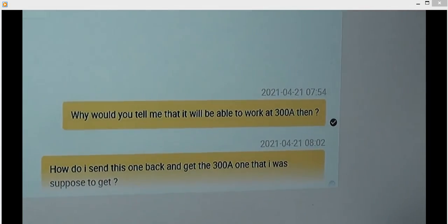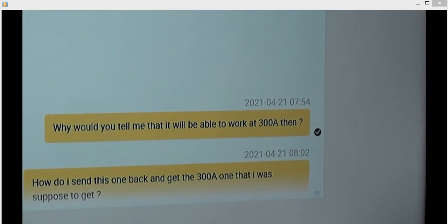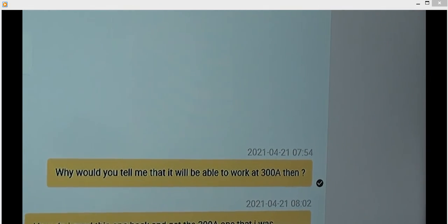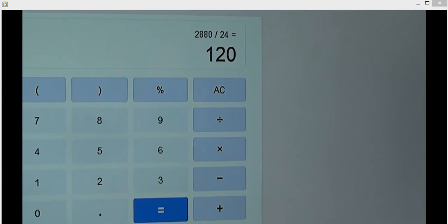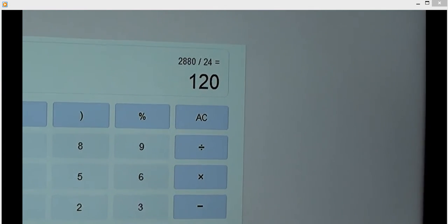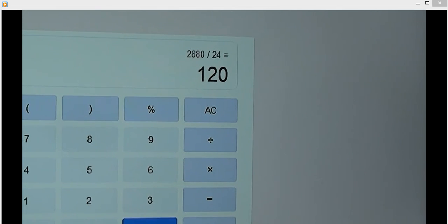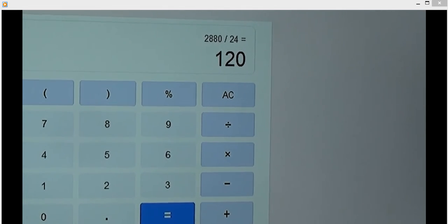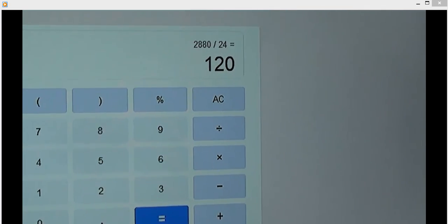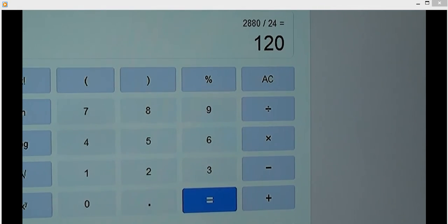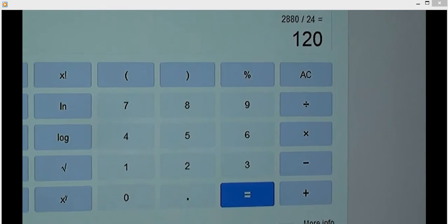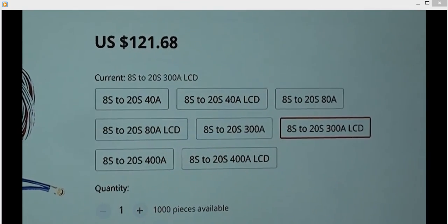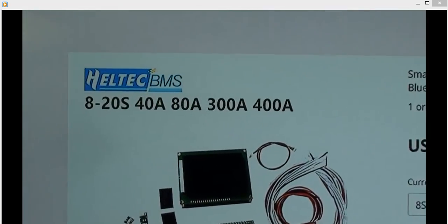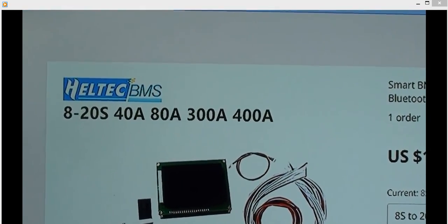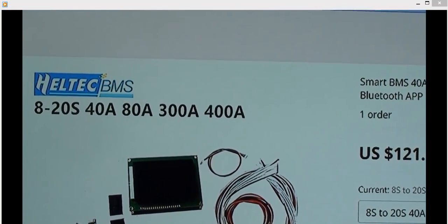Why would you tell me it would be able to work at 300 amps then? How do I send this one back and get the 300 one that I was supposed to get? Or 2,880 watts divided by 24 volts is 120 amps. So that means it's only supposed to be able to handle a 2,500 watt inverter, not the 6,000 watt inverter that I got. But this is what I ordered, and I don't see 120 amp continuous BMS listed on this page.